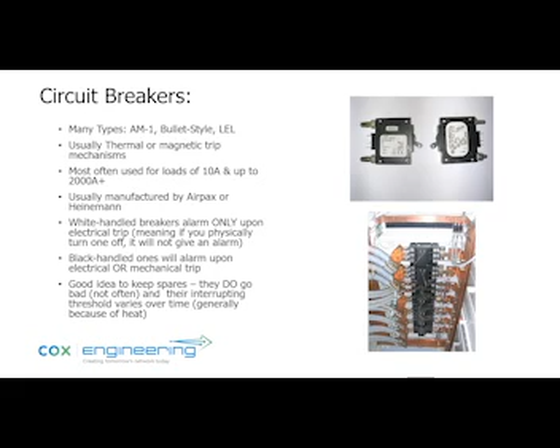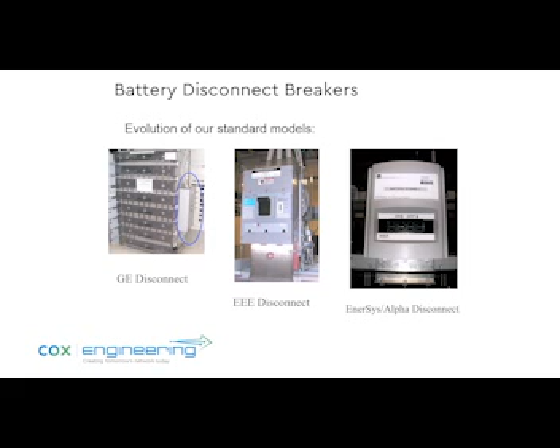Battery disconnect breakers are another form of a breaker, of a disconnect. So every battery string typically has a disconnect. Some of the telcos used to not do that. I think most of them do now, not all of them, but they didn't want to have any single points of failure. But you want to make sure that the battery disconnect is sized properly so that it could take the full load of amps that are going out of that battery or into it in recharge.